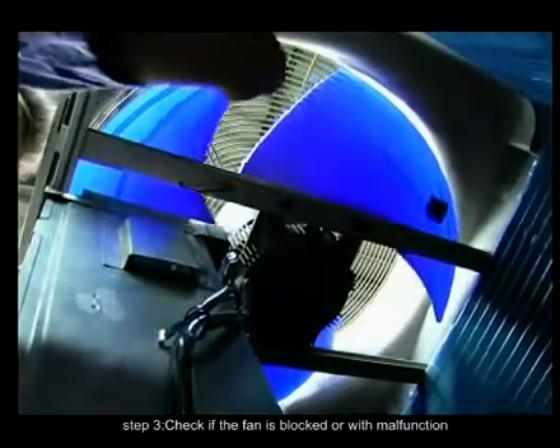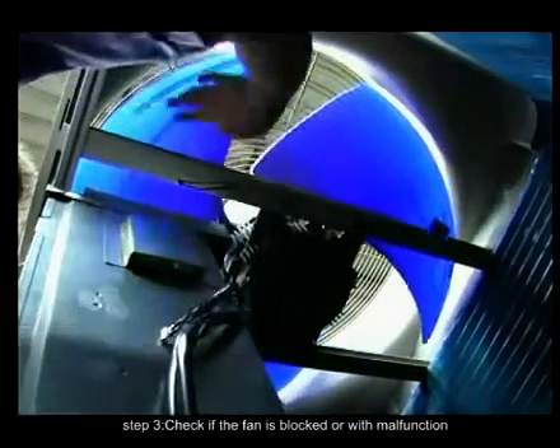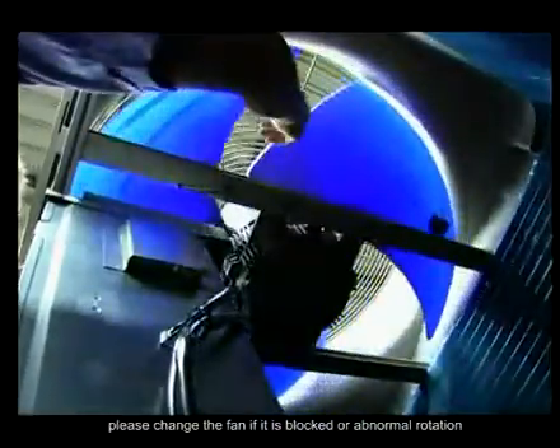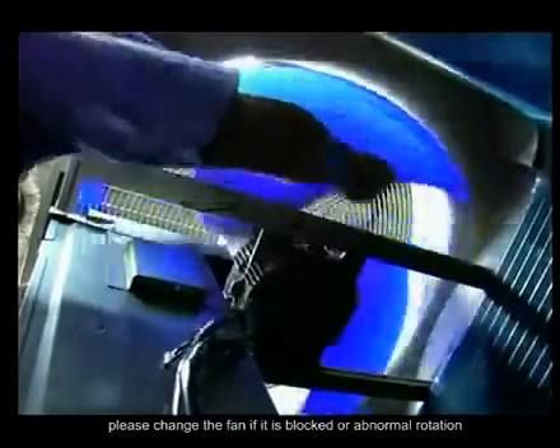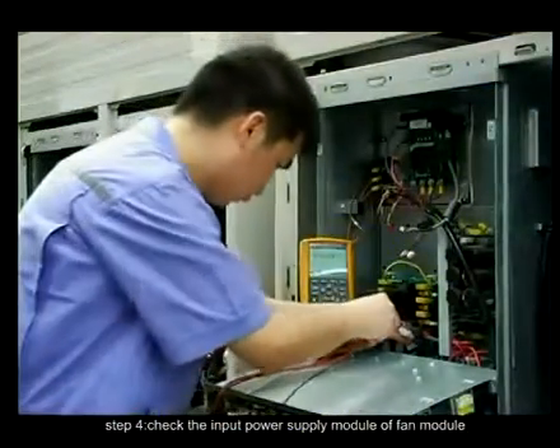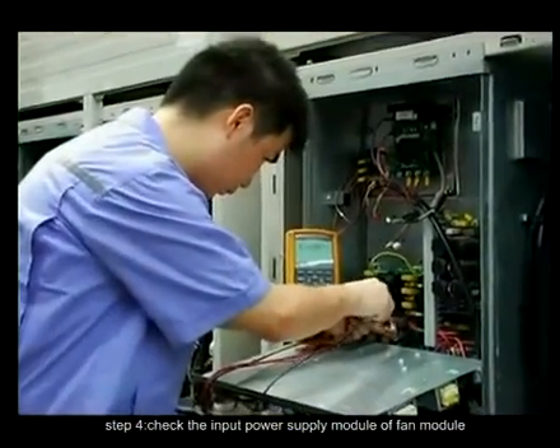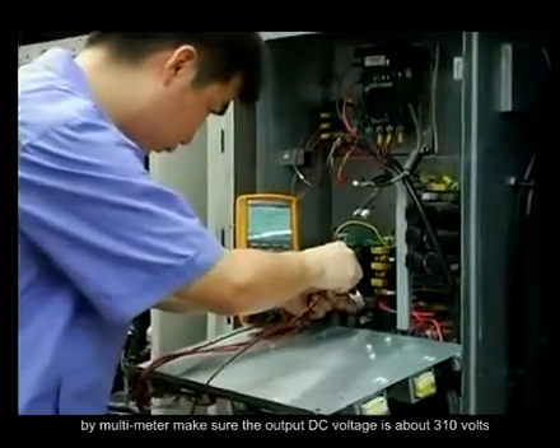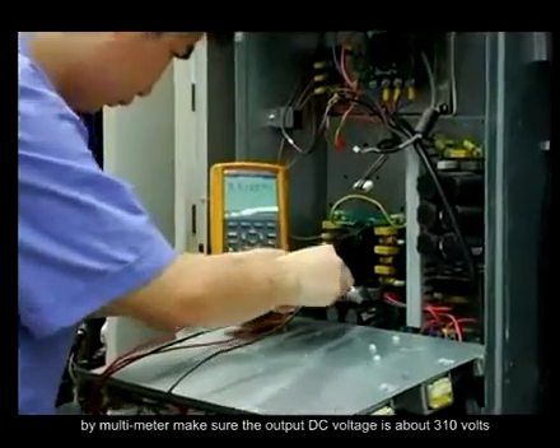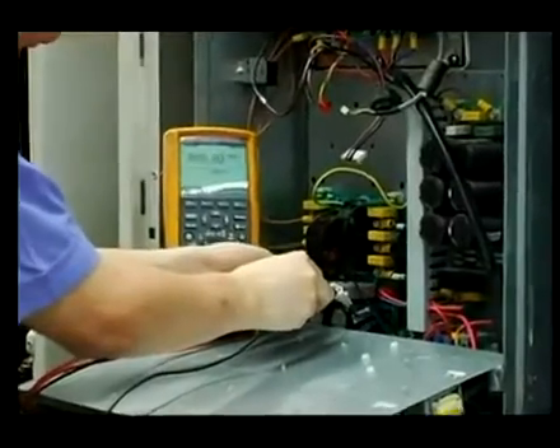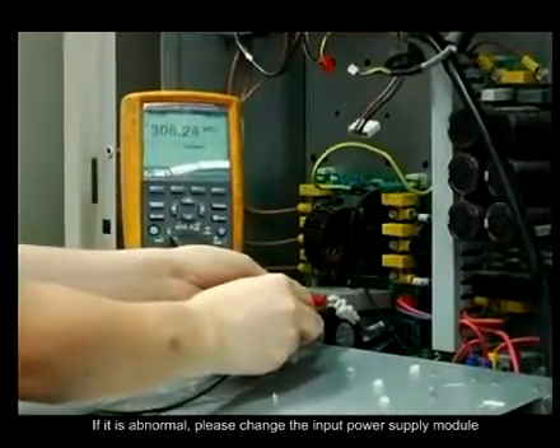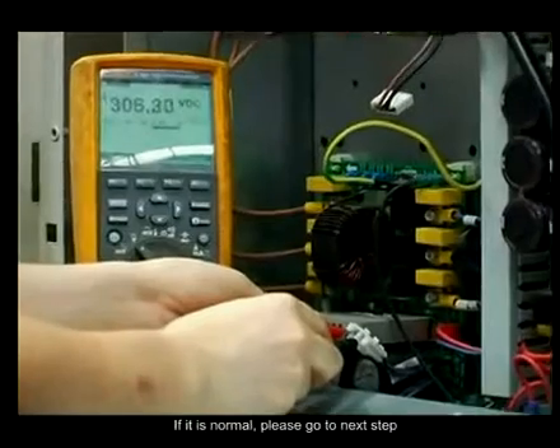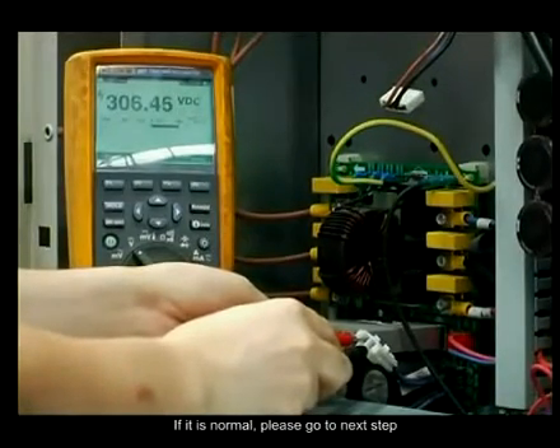Step 3. Check if the fan is blocked or has a malfunction. Please change the fan if it is blocked or rotates abnormally. If normal, please go to the next step. Step 4. Check the input power supply module of the fan module with a multimeter. Make sure the output DC voltage is about 310 volts. If it is abnormal, please change the input power supply module. If it is normal, please go to the next step.